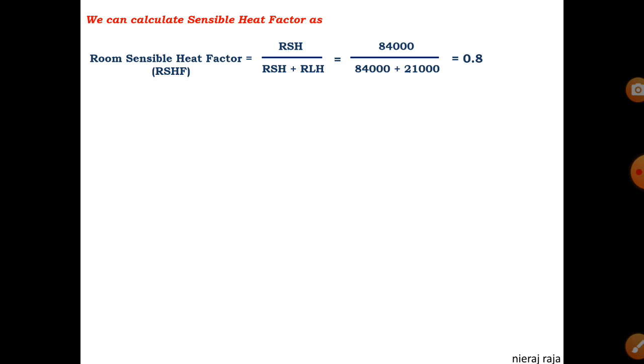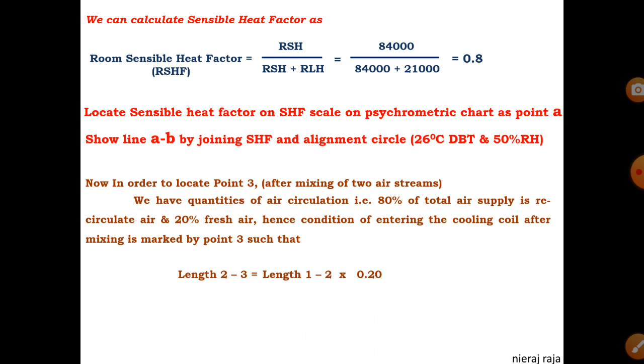The RSHF value of 0.8 is an alignment circle value that you will locate on the psychrometric chart. There is an SHF scale on the right side, near the humidity vertical line. Mark point A at 0.8 on the SHF scale, and mark point B on the alignment circle, which is always at 26°C DBT and 50% RH. Then join points A and B. Draw a parallel line through point 2 to get the RSHF line.